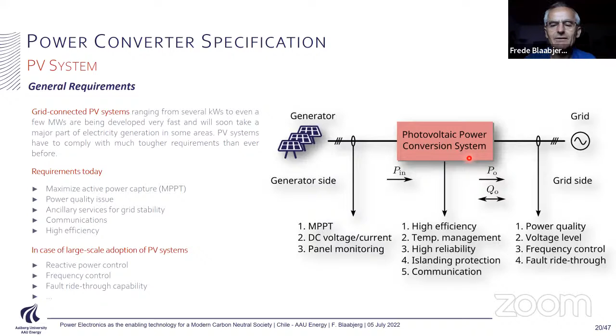What is also a demand typically for this kind of technology is that it should be able to detect if the grid is disappearing, because otherwise there's a risk that this one here can operate like a real grid without detecting it. So there should be some islanding protection. And here you can see the different ways of realizing the photovoltaic technology from a converter per module. You can see here either with two stages or one stage. Here you have a DC converter per panel, and then you have a DC bus and then DC-AC.